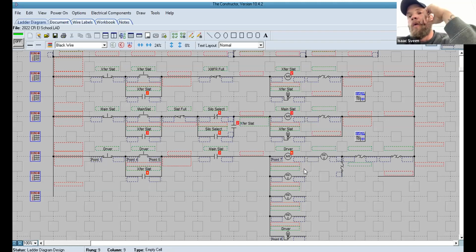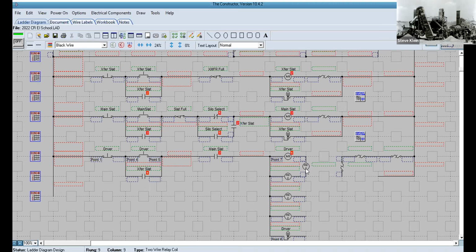So if it were just one motor, you typically do that in series then? The motor coil to the overload stays in series. However, when you have multiple motors, let's say I've got a motor on each part of the drum here, you then end up putting all the coils in parallel like this.